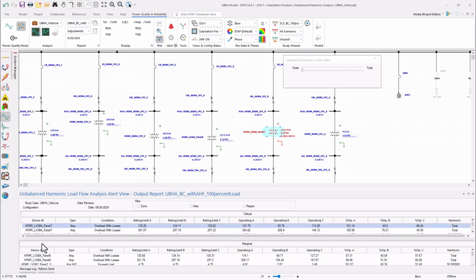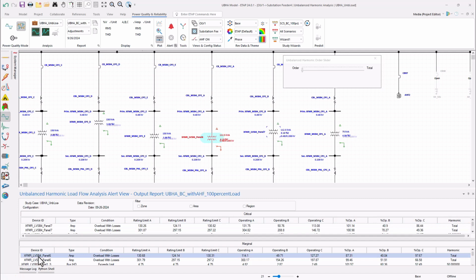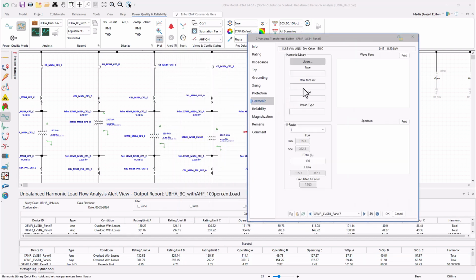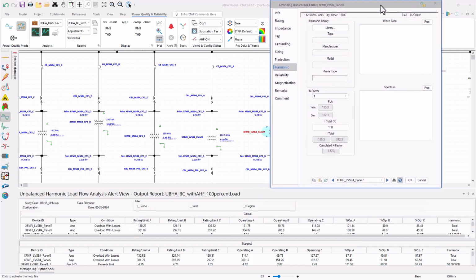Transformer LVSB4 panel 7 and transformer LVSB4 panel 6 are both flagged for derating condition. If we open one of the transformer editors and go to the harmonic page, we see the rated ampacities of the windings of this transformer are given here. But capacity ratings that we see under ratings in the alert view are lower than this. So these are calculated using the derating factor, and currents passing through the transformer are compared against the derated values, and derating requirements are flagged in the alert view for the devices with the condition overload with losses.